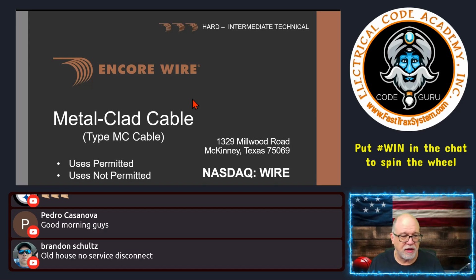A lot of the jurisdictions that I run into, well, if there's no service disconnect at all and you do a change, I'm sure that regardless of what the NEC says, once you touch those legacy systems, and I had an old house like that years ago, where the panel was just a bunch of Edison-base fuses, and it was inside of a bathroom, believe it or not. The service conductors came through the house, and as long as I left it alone, nobody had a problem with it. But the moment I started touching it, the local AHJ had rules that required me to bring it up to code. So again, it's not really something the NEC can govern, except for the things I told you about, but you need to talk with your local inspector and see what they say. Brandon, that's the best I can help you with that.